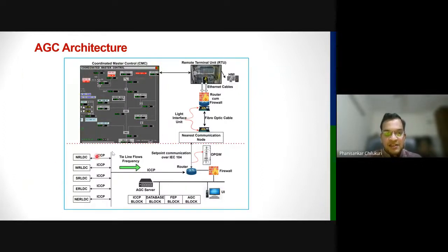We source all the data from the RLDCs, the tie line flows and frequency data, through router and firewall. We give the AGC set point on the IEC 104 communication protocol. So what I urge all the students is that you also try to read up on communication protocols, because the next generation of power systems is going to be fully based on IT and communication. Reading classical power systems is needed, but you also have to read up on the latest protocols, particularly IEC 104, the newer smart grid protocols and all that.